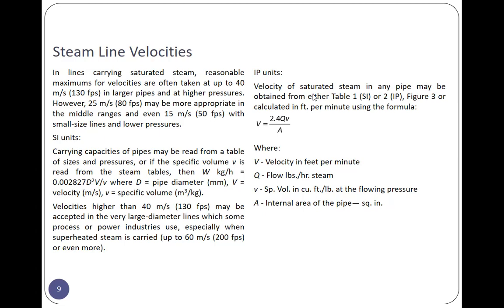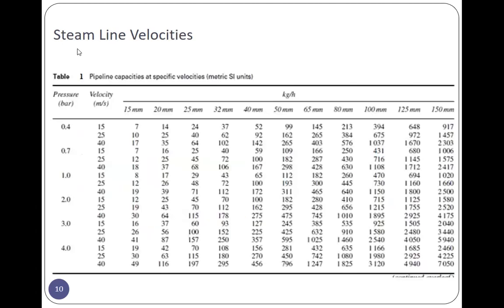IP units, velocity of saturated steam in any pipe may be obtained from either table 1, SI, or 2, IP. So ito yung figure. Figure 3, or calculated in feet per minute using the formula v is equal to 2.4 times Q V over A, where v is the velocity in feet per minute, Q is the flow in pounds per hour of steam, V is the specific volume in cubic feet per pound at flowing pressure, and A is the internal area of pipe. So ito yung steam line velocities.